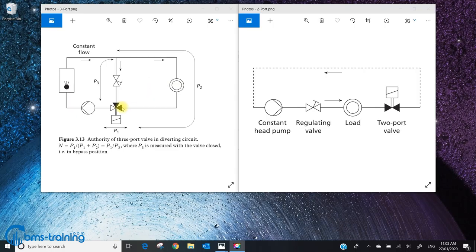So we generally used to try and match the pressure drop across the fully open valve with the pressure drop across the coil. So if we had 10 kPa across our coil, we'd try and size the valve and select a kV as close as possible to 10 kPa across the valve, and then we have 10 divided by 10 plus 10. So that would be 10 divided by 20, and that gave us a valve authority of 0.5, which is ideally what we're aiming for, or slightly higher, but definitely not lower. If you get down to about 0.25 valve authority, a valve won't work. And there's a whole bunch of things there that we're not going to go through today. So that was really easy.